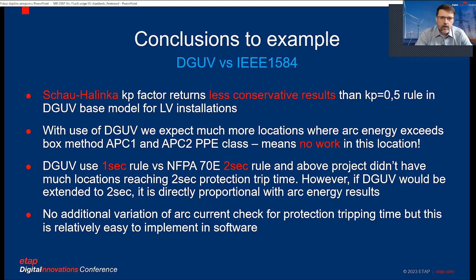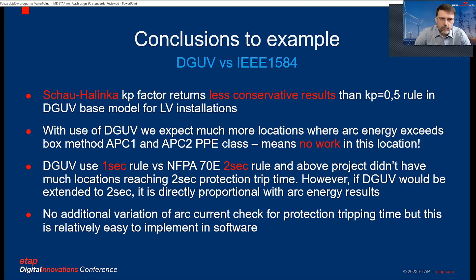Most protective devices will sometimes work much longer than one second — five seconds is the required maximum automatic disconnection time for distribution feeders in low voltage. So limiting to one second is rather optimistic. Also, there is no additional variation for arc flash current — no check for jumping between instantaneous settings and short trip time settings — though it's kind of included via minimum arc variation based on minimum short circuit current.